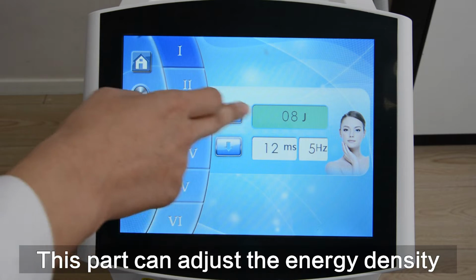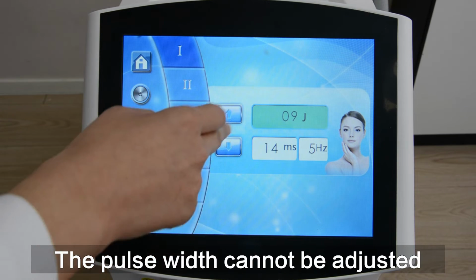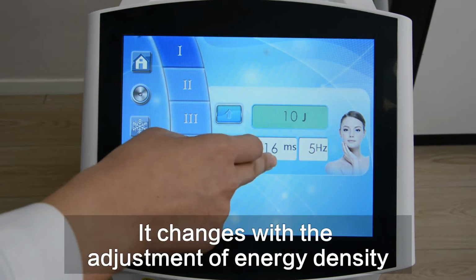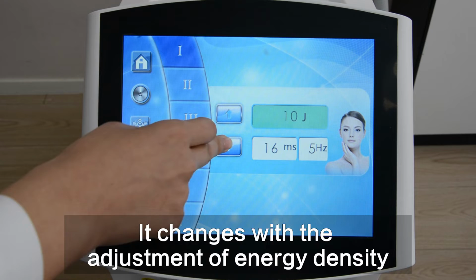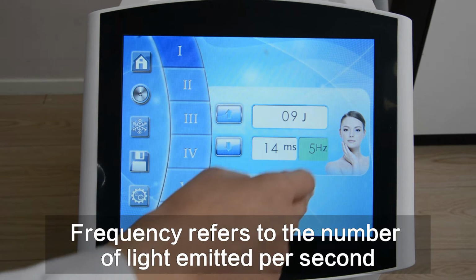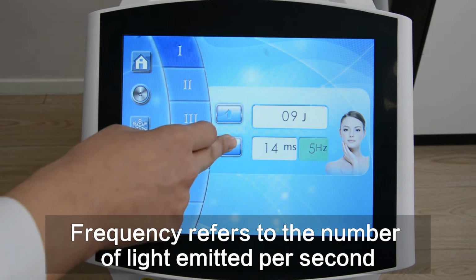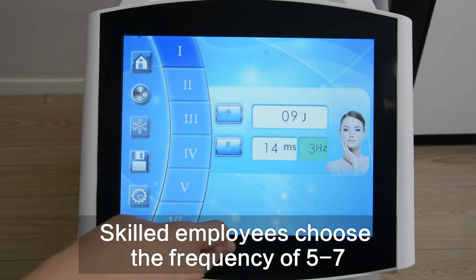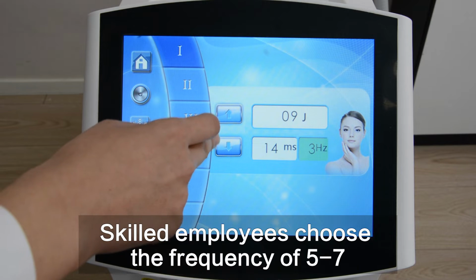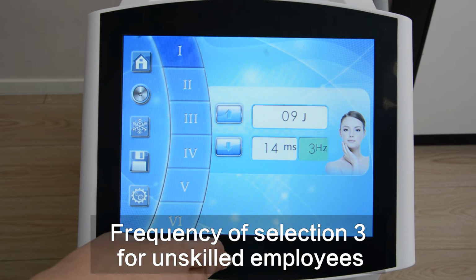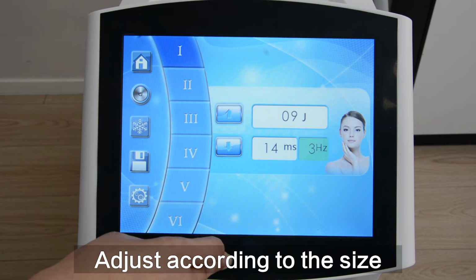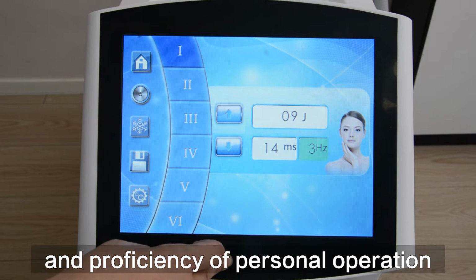This part can adjust the energy density. The pulse width cannot be adjusted. It changes with the adjustment of energy density. Frequency refers to the number of light pulses emitted per second. Skilled employees choose a frequency of 5-7. For unskilled employees, choose a frequency of 3, and adjust according to the size and proficiency of personal operation.